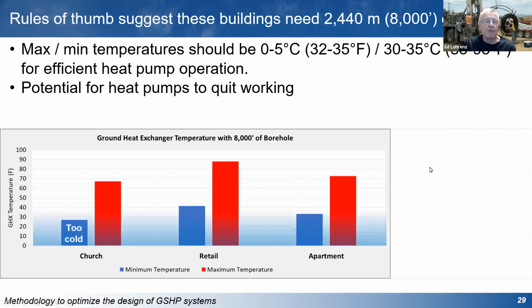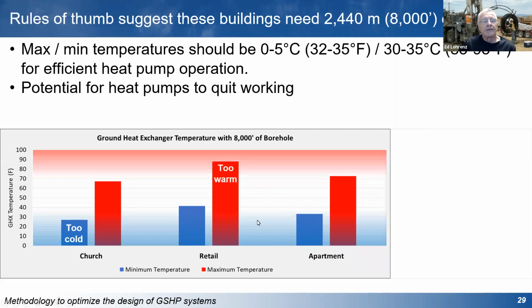So one of the buildings is going to get too cold, the church, because you've got less cooling load, less heat rejected to the ground. That has the danger of getting below those temperatures. And the retail store, because you're cooling a lot more, is going to tend to get a bit too warm. It's going to get well above 90, 95 degrees.